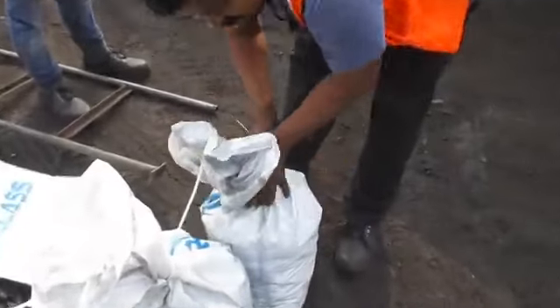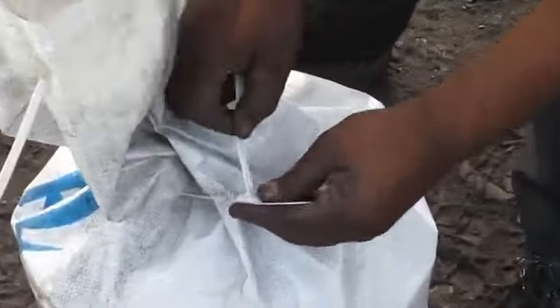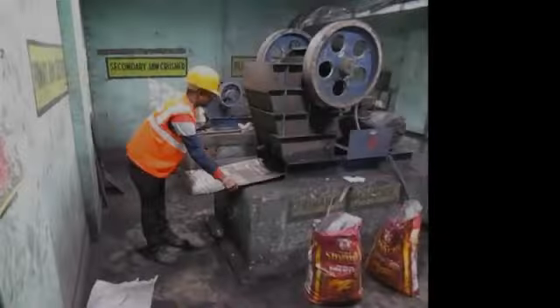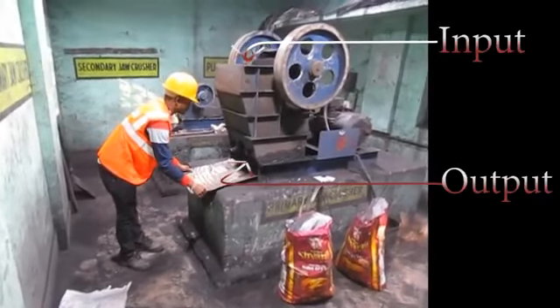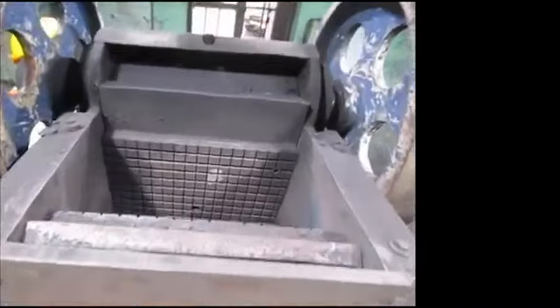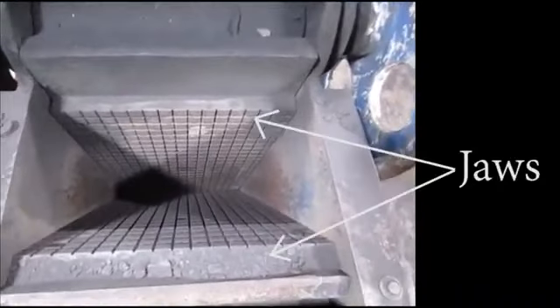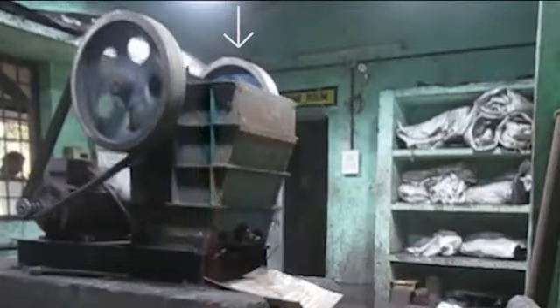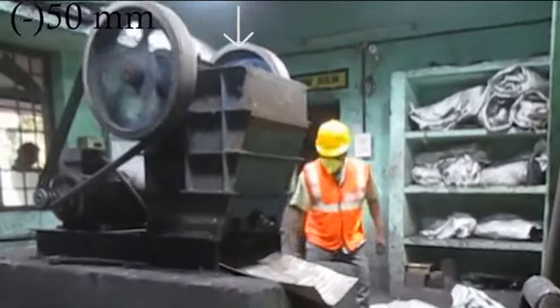Samples are sealed using tags and are transported in such a manner so as to make these tamper-proof. The samples are transported to the coal sample preparation room. This is a jaw crusher which can reduce the size of the coal samples to less than 50 millimeters. This is also called the primary crusher.